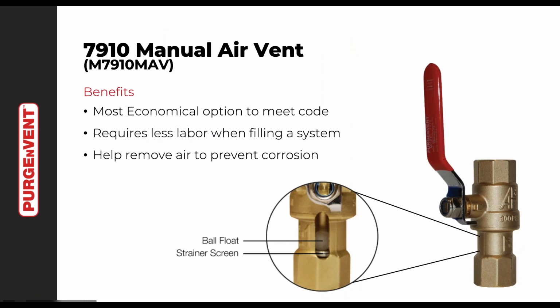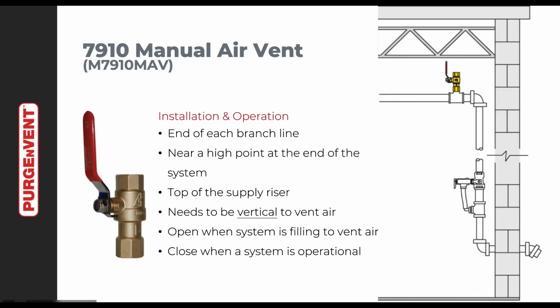So first and foremost, the first choice in the code was that you could have our model 7910. It's a manual air vent. Although we call it a manual air vent, it's much more like a semi-automatic air vent. It utilizes a Teflon float ball in it that's between the inlet of the valve and the ball that seals it. So that ball would bounce around like you'd see inside the ball inside of a sports whistle, and it would let all the air out until water comes up underneath it, and then the water is going to push the Teflon ball up into the main ball of the valve and seal it closed. So it's kind of semi-automatic in that it won't gush out water once water comes up to the unit, and then the unit can be operated to let out any residual air. We typically see these put on the top of the pipe at far ends of systems.